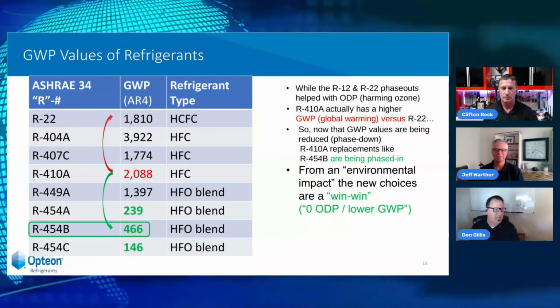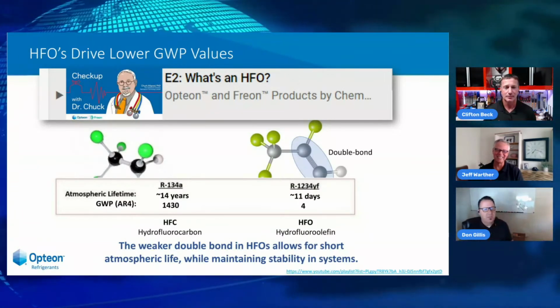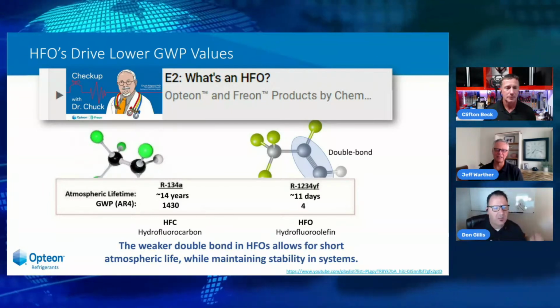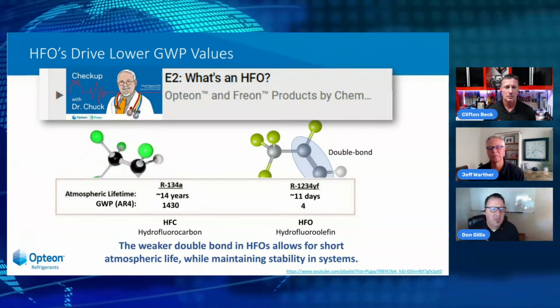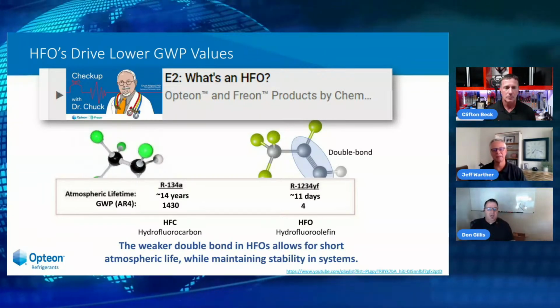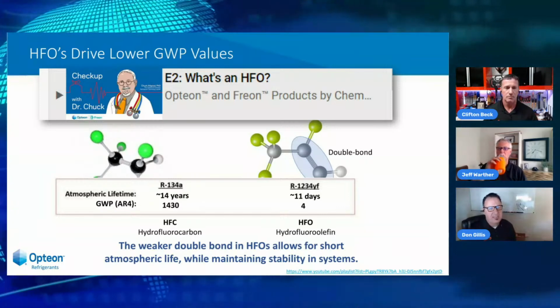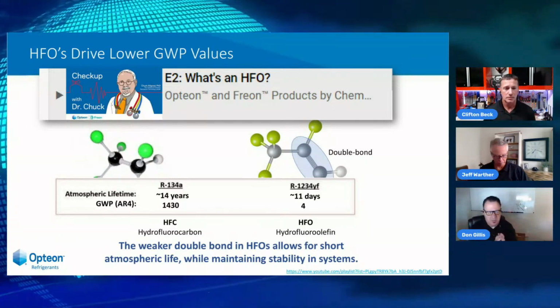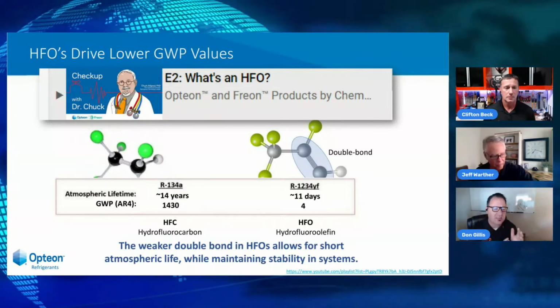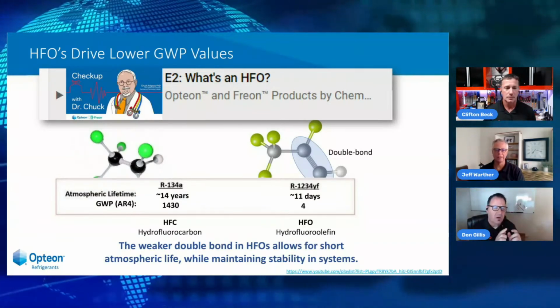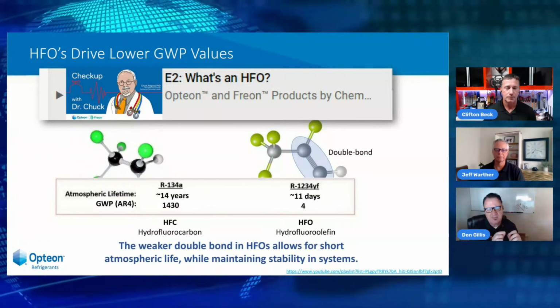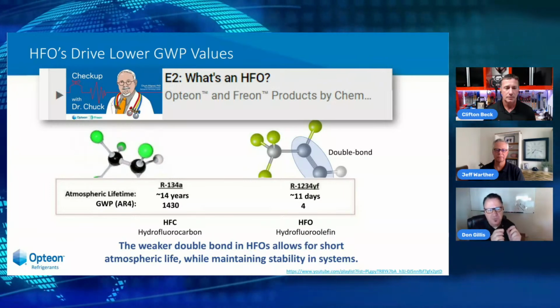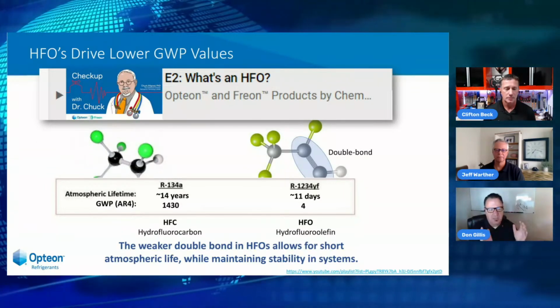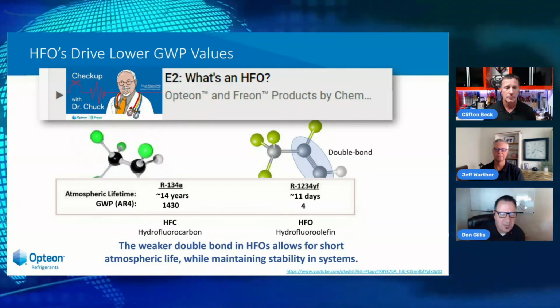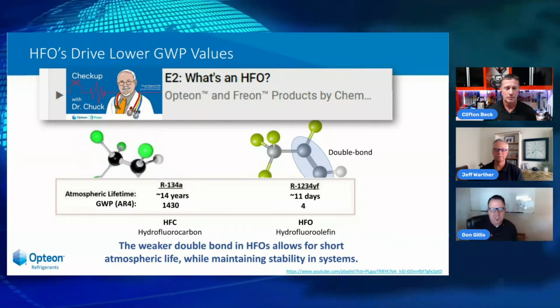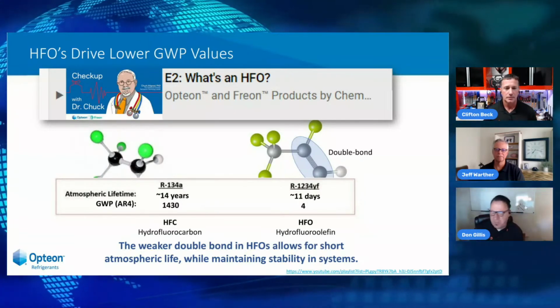Let's slip onto the next slide. So here we're talking about what's blocked on the screen as 1234YF, but really what they're saying here is HFOs. They're double bonded, and what that means is they break up easier in the atmosphere. Those two molecules are carbon molecules, and anytime you have two molecules that are the same connected, it's referred to as double bonded, and they break up much quicker. The example they're giving is the difference from 134A at 14 years in the atmosphere as opposed to 12 days for 1234.